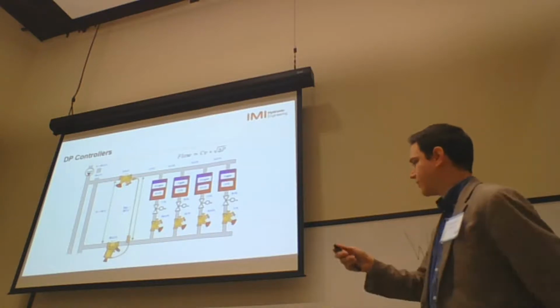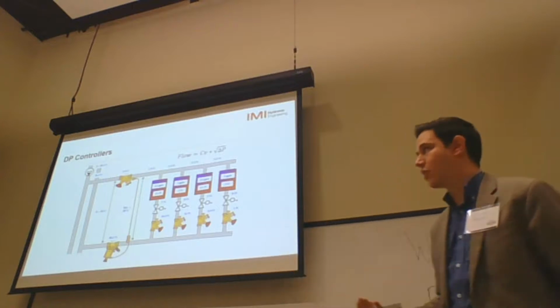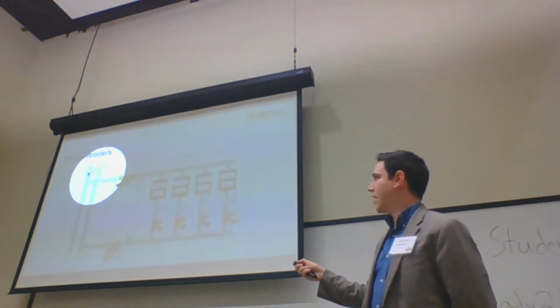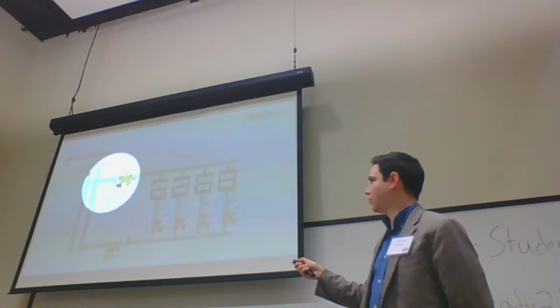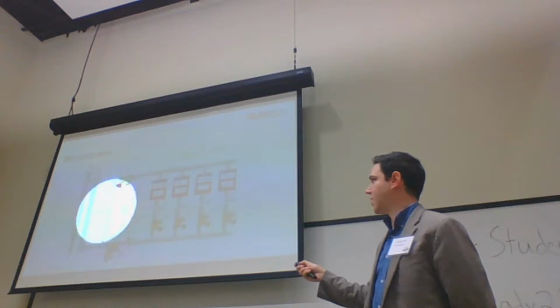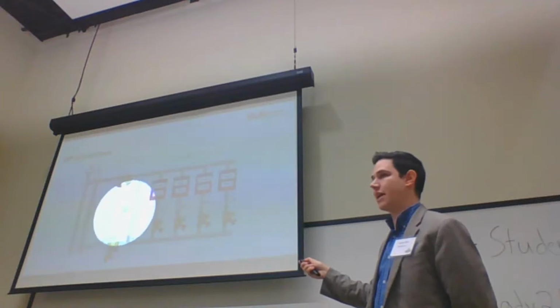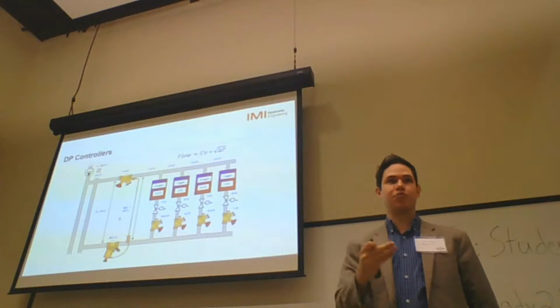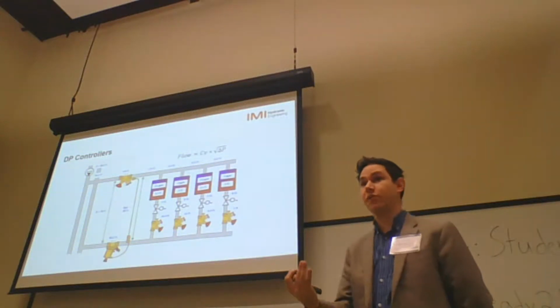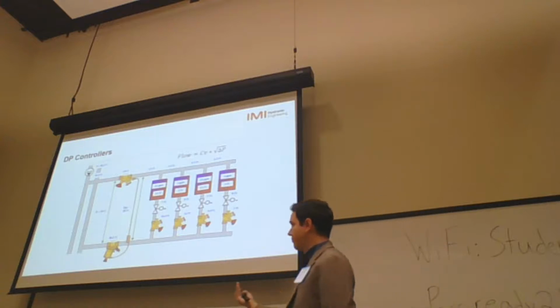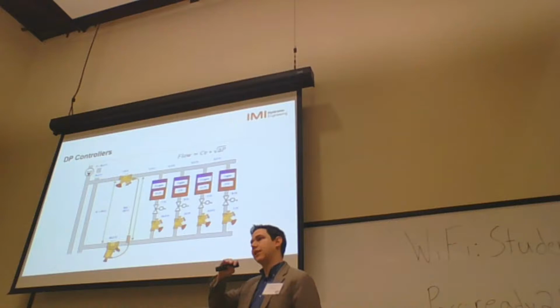So in this example, to understand how it works, the concept or the mechanical parts of the valve: here I have the pump, 80.2 feet as my pump head. I have 10.2 feet as my pressure drop closer to the mechanical room and this part. So that leaves me 70 feet of differential for this first branch. There's a continuation for other branches right there. But in this first branch, I have 70 feet. These 2 valves are basically reducing the differential pressure from 70 to 28 and making the 28 stable for this branch. So this is how the technology of a differential pressure controller works. It is reducing the available pressure going to that branch and making that number stable.